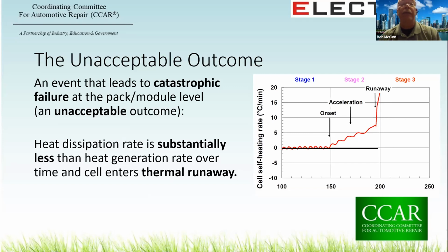You see that here in this plot. What you're looking at is the heating rate of the cell in degrees Celsius. As we move across the x-axis, starting from 100, we heat at about 1 degree a minute, maybe a little less, till we get out to about 150 degrees. At 150 degrees, we start to ramp up. We're into acceleration from the onset point. And then in this particular case, at 190 degrees, the thing goes vertical. This is the point of no return.